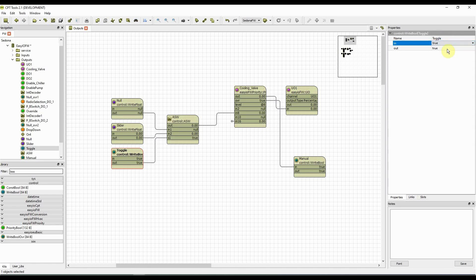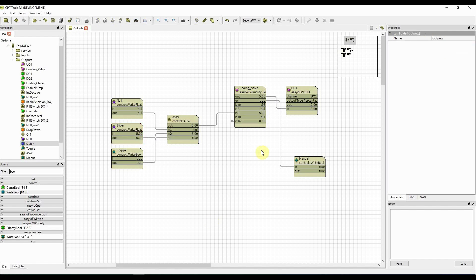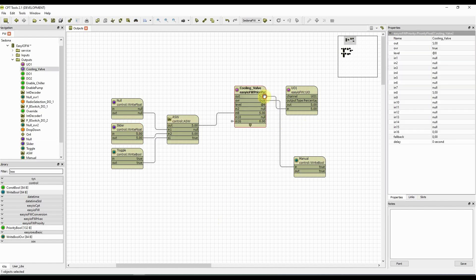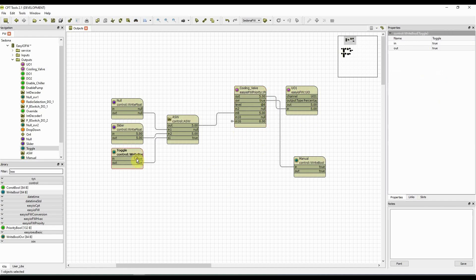So setting the toggle object to true will cause the slider's signal to pass. And if the toggle is set to false, value null will pass, so input 8 is null, and the priority block looks at input 15 or 16 which comes from the control strategy.